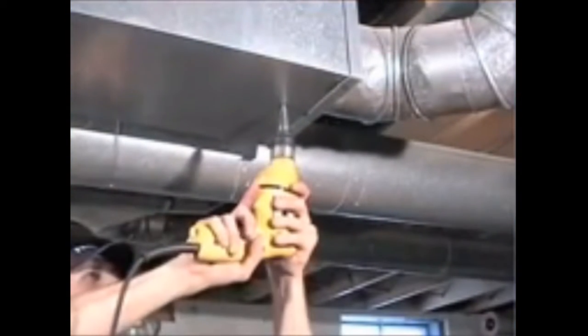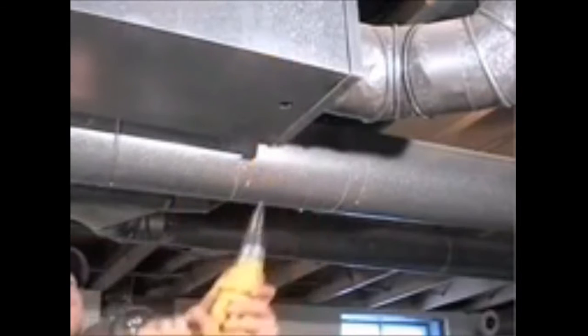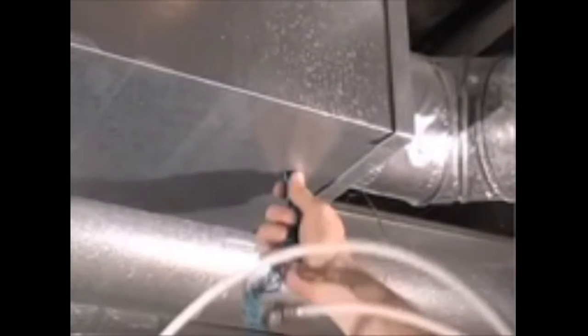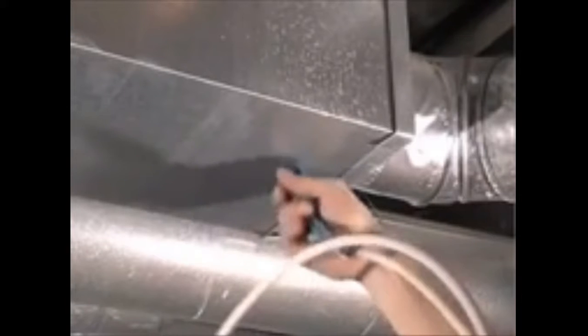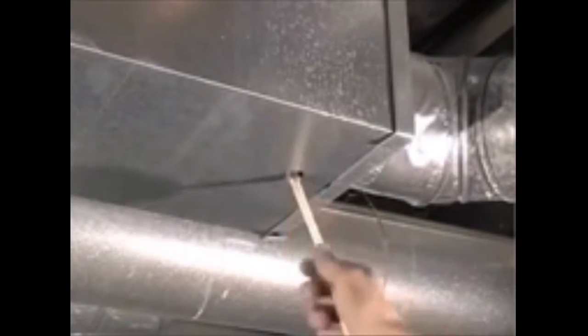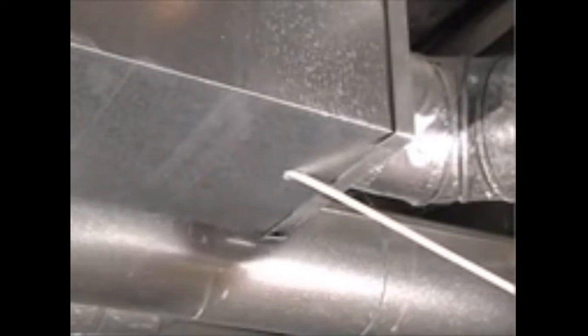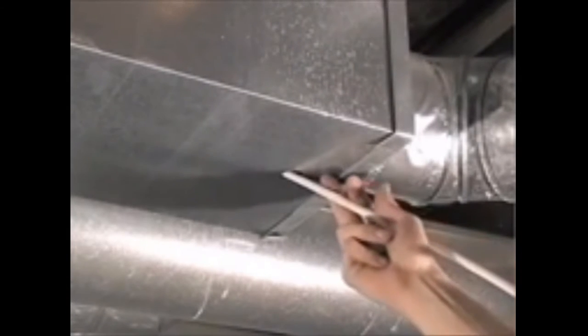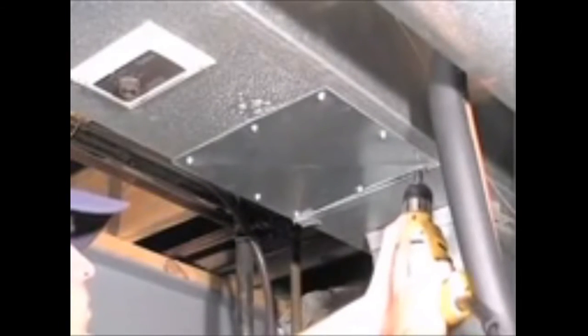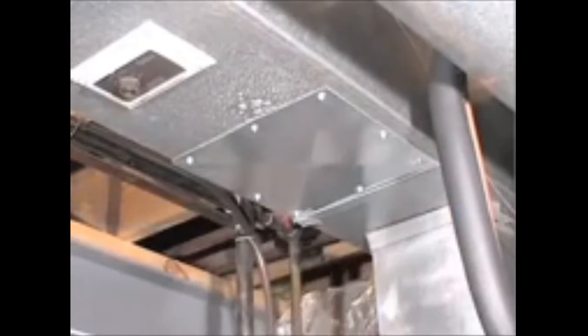We start by drilling a 1-inch access hole at the far end of the trunk line. The Viper is inserted and scrubs the walls of the line while driving the material into the waiting vacuum hose. The extension rods and high-pressure air hoses will extend the full length of even extra-long runs. The light gray plastic plug and a new access panel close everything back up and seal the system against any loss of airflow or pressure. The final step is the air washing of the blower fan and the heat exchanger to remove any loose dust that may have accumulated. We don't recommend unhooking or removing any mechanical parts inside the furnace.